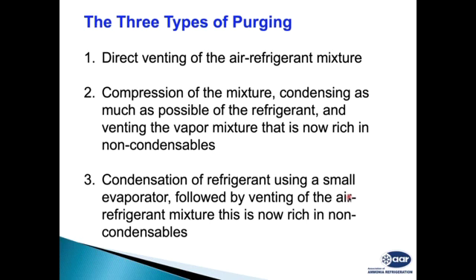Let's see what these two types of purging are, automatic and manual. And then there are again two types of automatic purging. One is compressing the mixture and condensing it using an external refrigerant device. Another is condensing the refrigerant using a small evaporator, using the refrigeration system itself, in which separate compressors are not used.